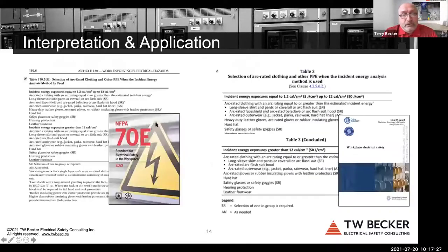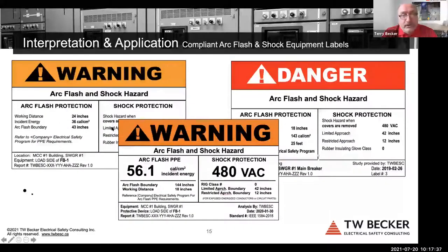So here's a quick excerpt of the two tables, again from 70E and Z462. When you have incident energy analysis, select clothing with an arc thermal performance value. The labels as well are a problem. These are compliant labels. We actually have an annex in Z462, Annex Q, that I wrote that's not in 70E, and the intent was to try and clarify what a compliant arc flash and shock equipment label should look like. And it should be ANSI Z535 based, right? This is what the label should look like.